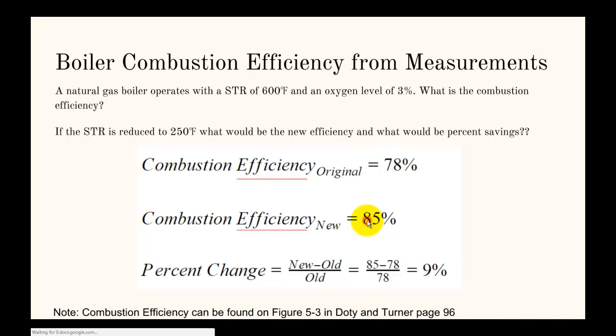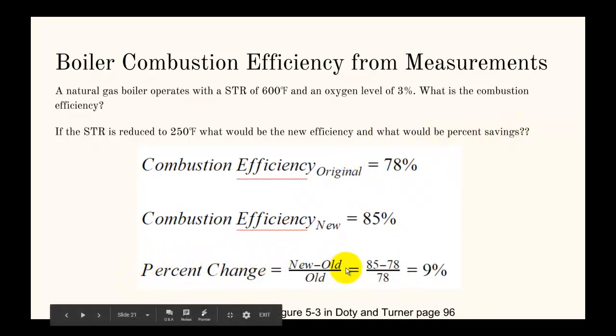Let's jump to our next problem. This is finding the combustion efficiency from measurements. Whenever you see a measurement of a stack temperature rise and an oxygen level or other measurements, you want to turn right to page 96 in Doty and Turner, which has the graphs you need. We're finding two different efficiencies here, one with an STR of 600 and oxygen level of 3, and then changing the STR to 250 degrees. We go from 78% to 85% efficiency. I ask what the percent savings is, and it's just a percent change formula: new minus old divided by old. In this case, it's 9%.